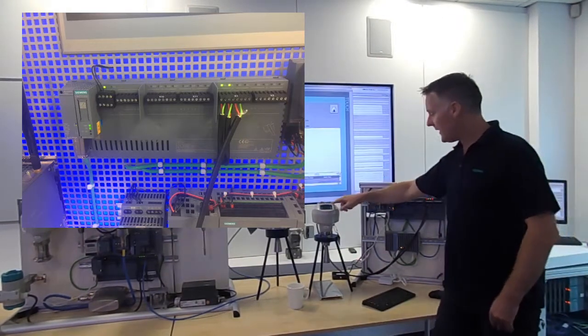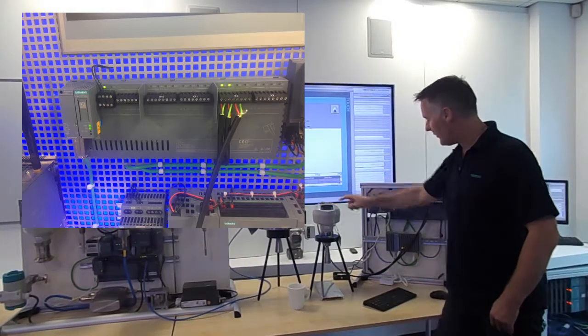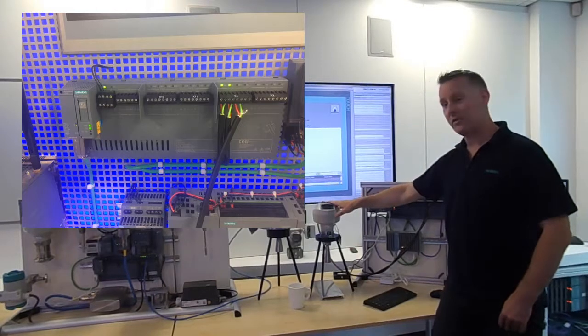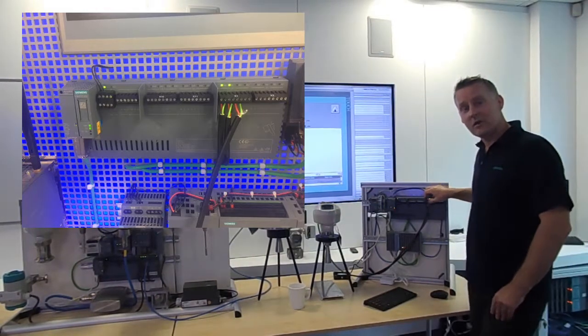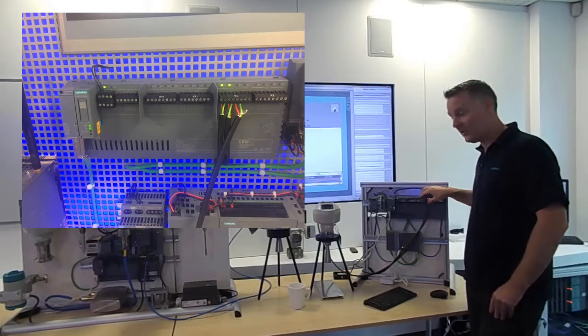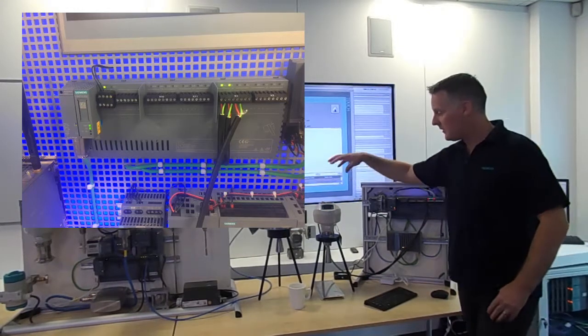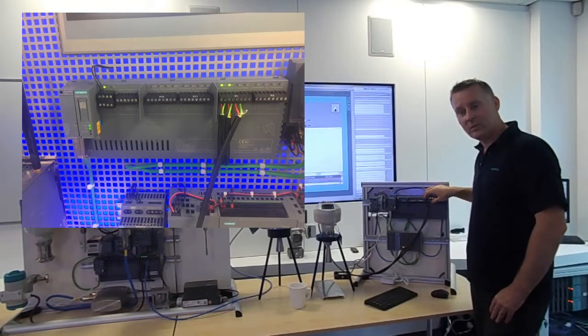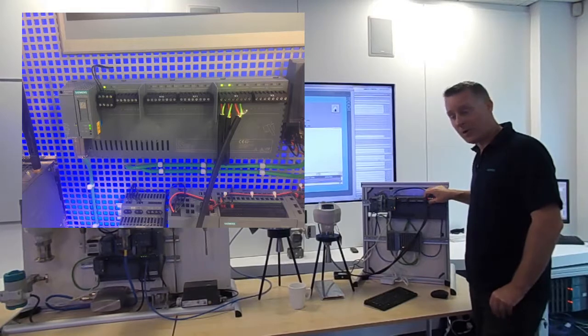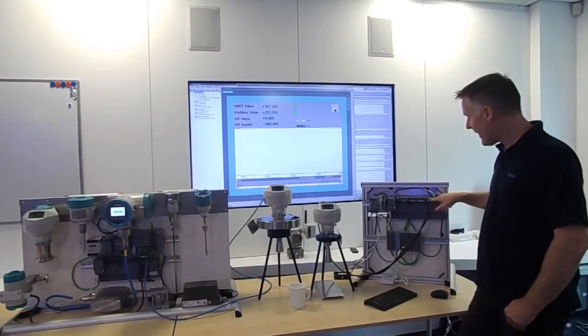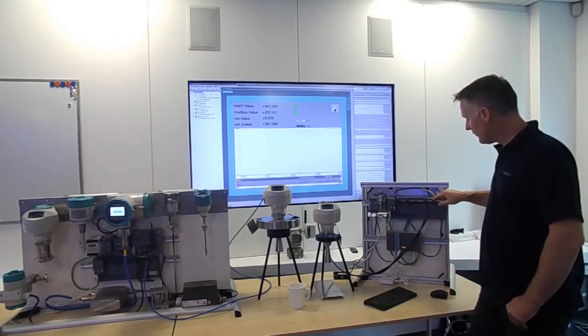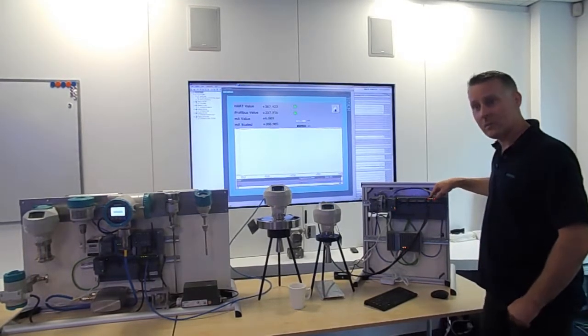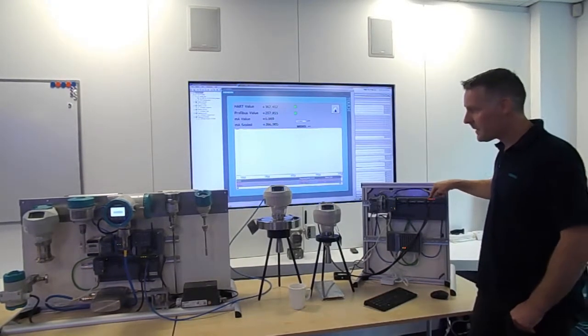So via here we normally have to use software to set the address. This will set the address of this unit. It also uses generic GSDs so you don't have to start putting manufacturer specific GSDs in here. So you can use other manufacturers with this kit without doing a download and a compile. It also monitors the voltage and current on each of its connections. So as we continue with the test we'll be able to monitor this and bring back additional diagnostics.